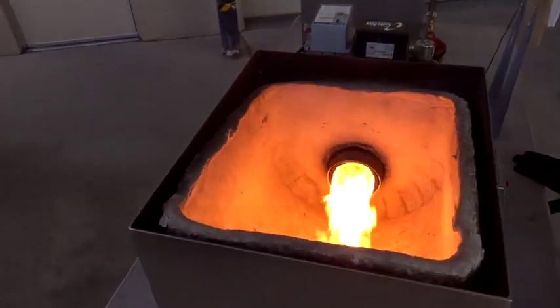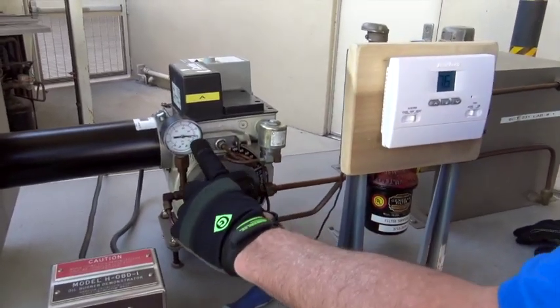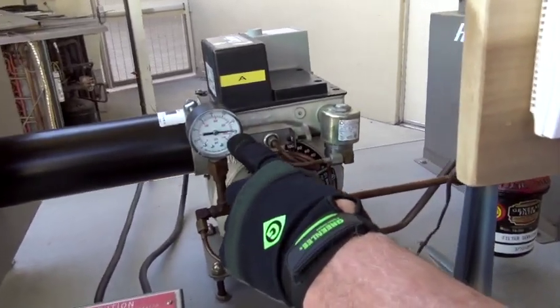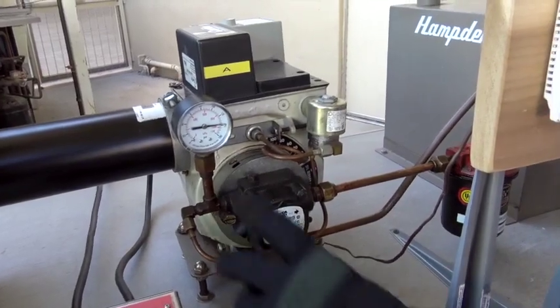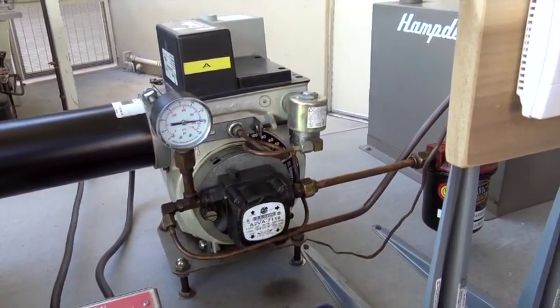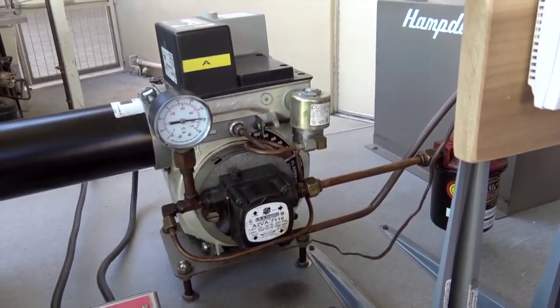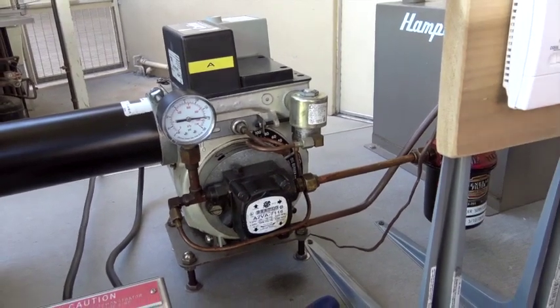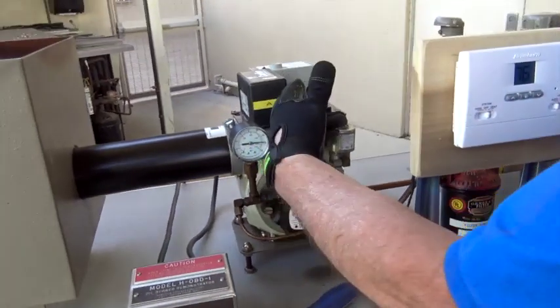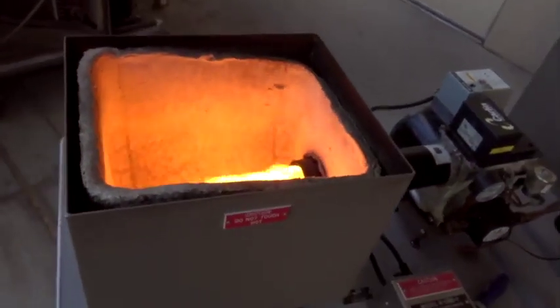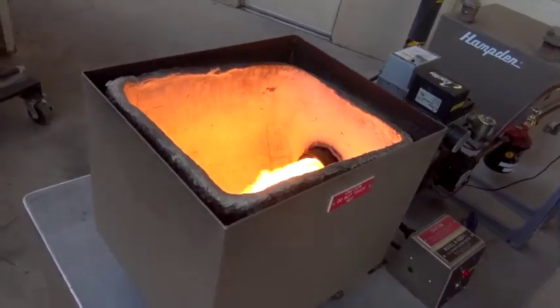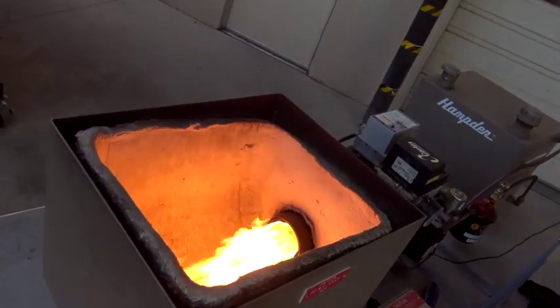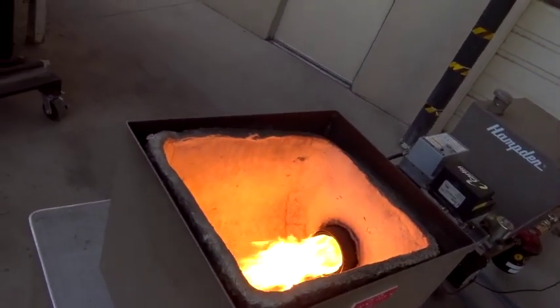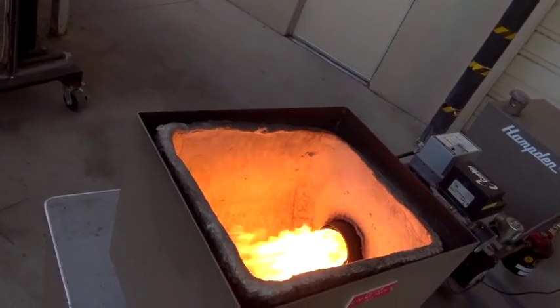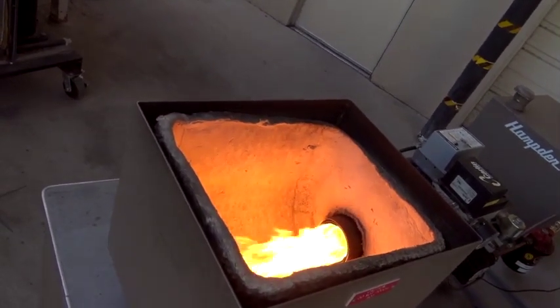And we have ignition. Look at the pressure. We're running about 140 pounds of pressure. Usually the minimum is about 100. As you see, we're right there at about 140 pounds, which is fine. Now we're pumping, we're also doing combustion air, and as you see, we do have combustion. Got a nice good fire ring on there all the way around. It's enveloped all around. Like I said, you would have a combustion analyzer checking this out.